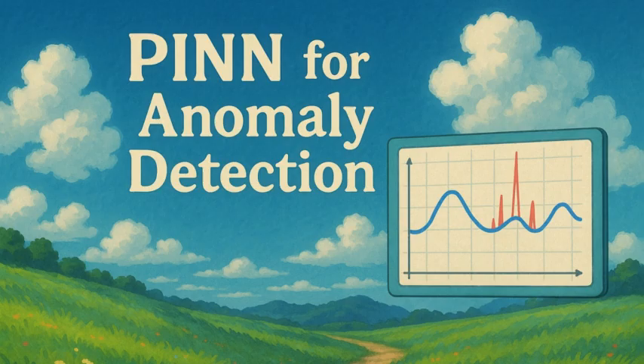Another huge hurdle is data — or rather, the lack of it. The classic data hunger problem, but amplified here. Good ML models usually need lots of data, especially labeled data showing both normal and abnormal states. But in a well-run industrial plant, major failures are hopefully rare — you don't want lots of anomaly data. So getting enough labeled examples of failures is tough. And even getting comprehensive normal data covering every possible operating condition, different seasons, different loads, is a challenge. If you train it only on summer data, it might flag normal winter behavior as an anomaly. It's a cycle — it can only learn from what it's seen.